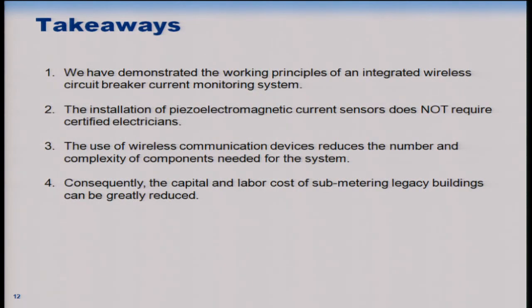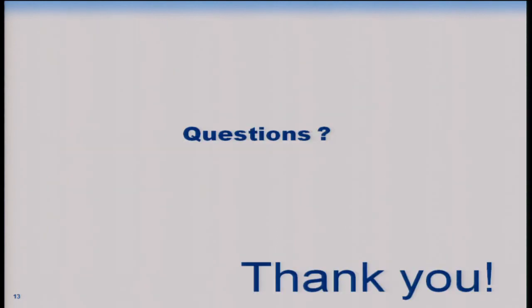Key takeaways: we demonstrated a working integrated wireless circuit breaker current monitoring system that does not require certified electricians to install, as sensors are placed on the surface of the panels. This greatly reduces cost and labor. Using wireless communication devices reduces the number and complexity of components, resulting in significantly lower capital and labor costs overall. That ends my talk — I'd be happy to take any questions.